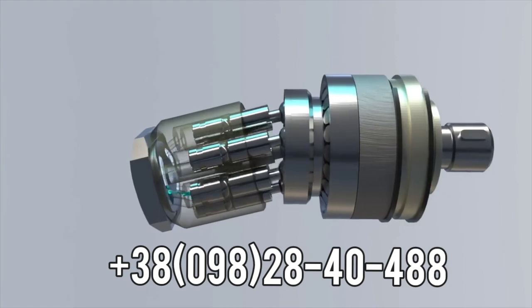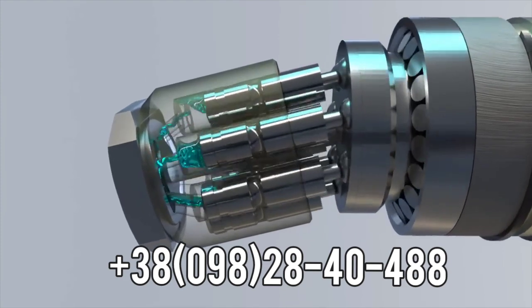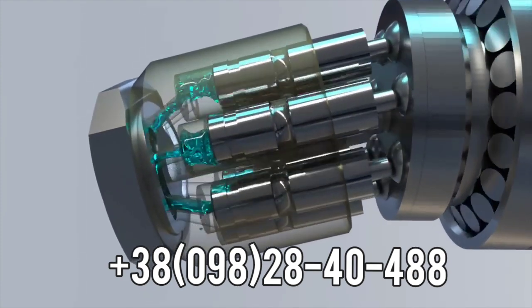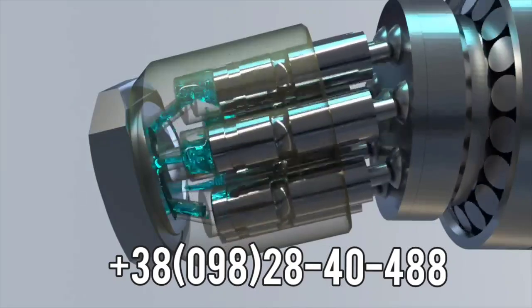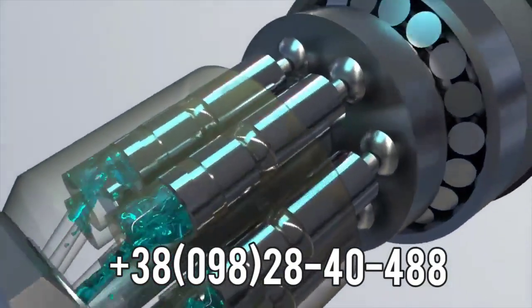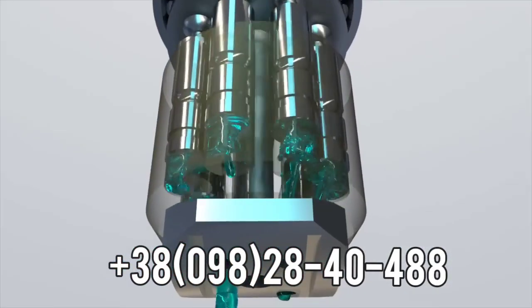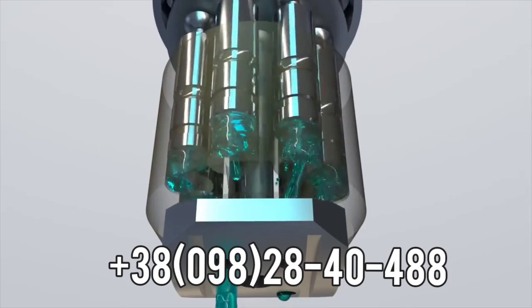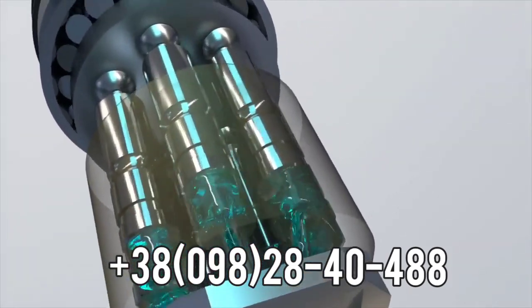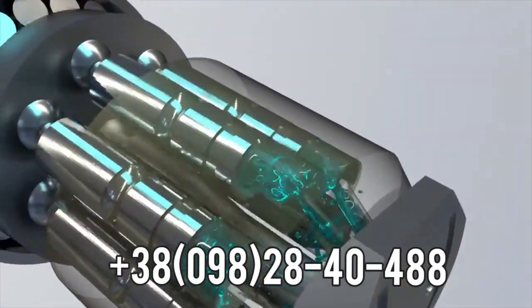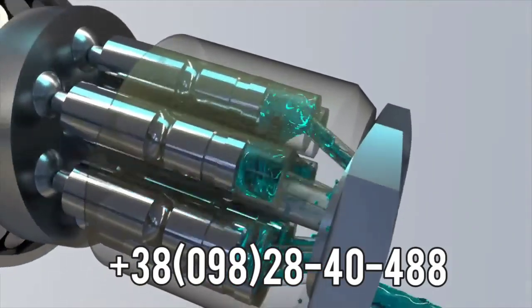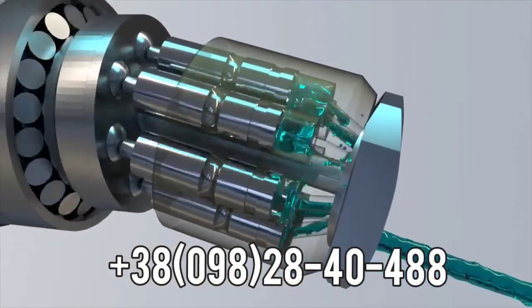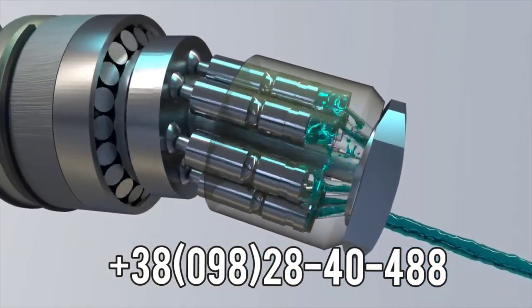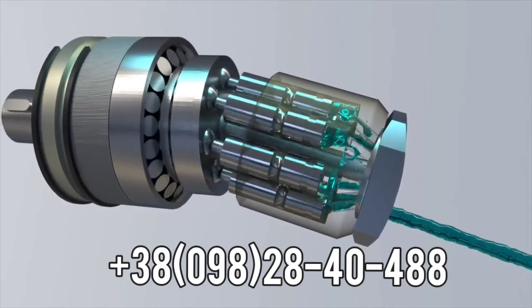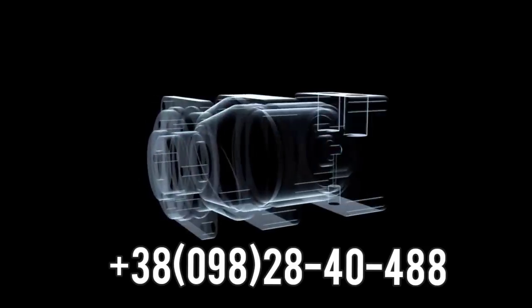Several pistons are installed in the pump housing. There are 7 in the example provided. While one piston performs suction, the other is pushing the fluid into the pressure line, and the third is in the extreme position. This design allows for a continuous supply of fluid with relatively low pulsations. The presented pump does not need any check valves, since its pistons always suck in one area and discharge in another. The design of swash plate pumps is different, but the principle of their operation is the same.